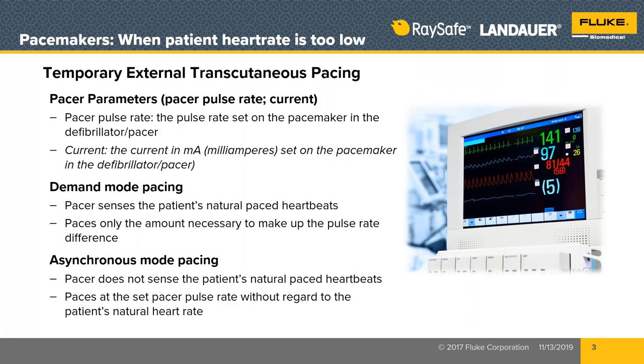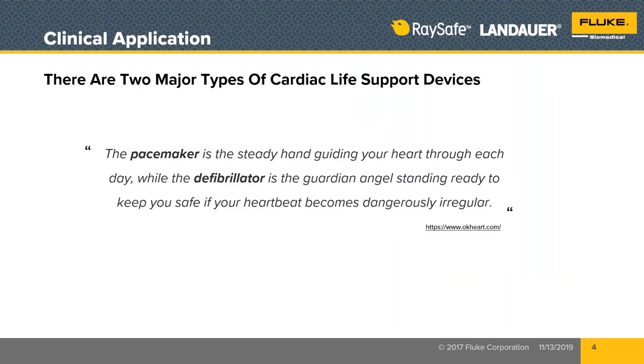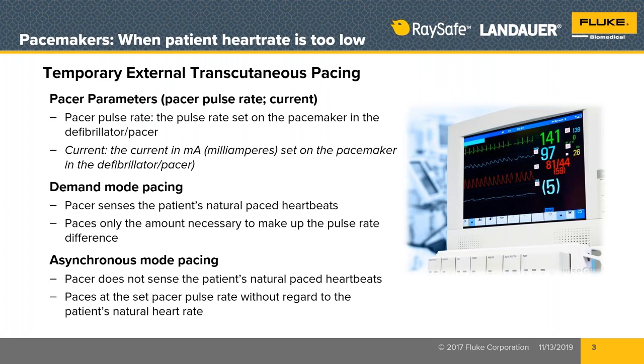Just want to make it clear that we're not testing implanted devices. Sorry, we're not testing implanted devices. So not implanted defibrillators nor implanted pacemakers, because when we do quality assurance testing, periodic testing on these medical devices, we purposely do not want the patient connected. We're going to connect our test instruments instead and do everything that needs to be done to verify the performance and safety of these devices. So just to make that really, really clear.